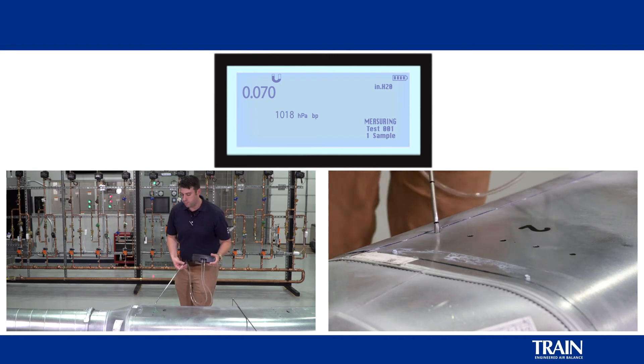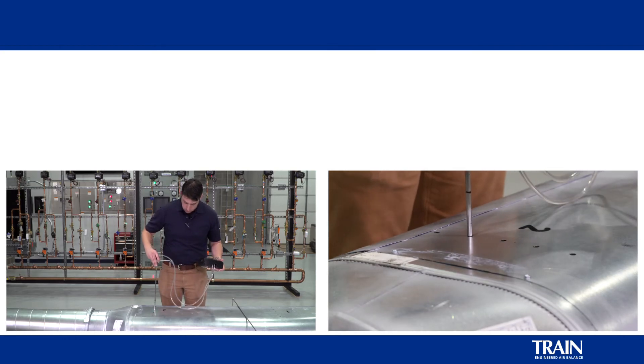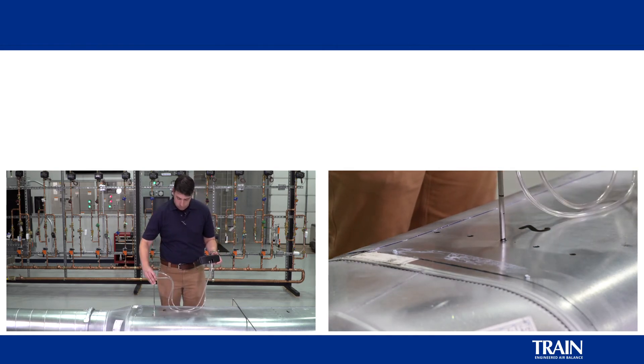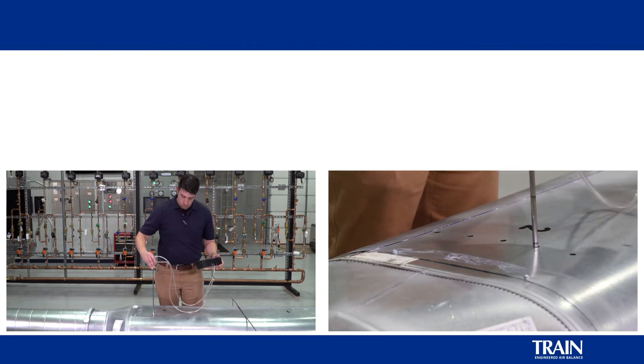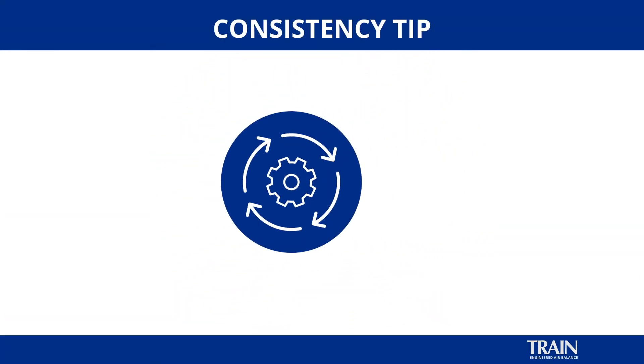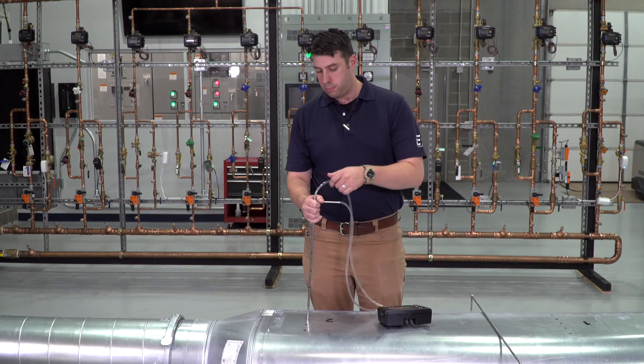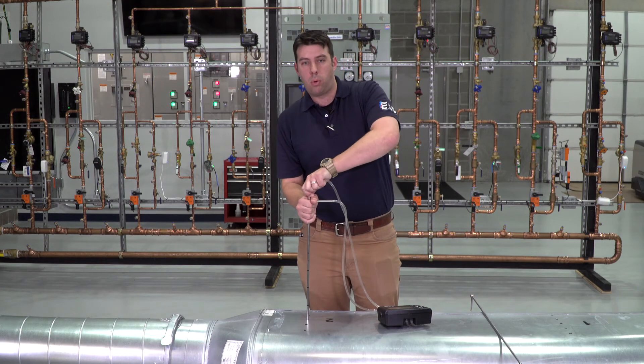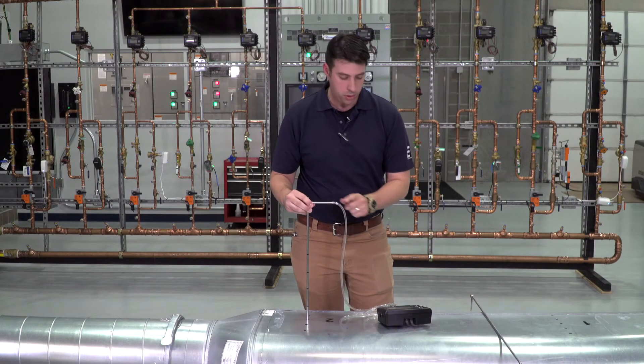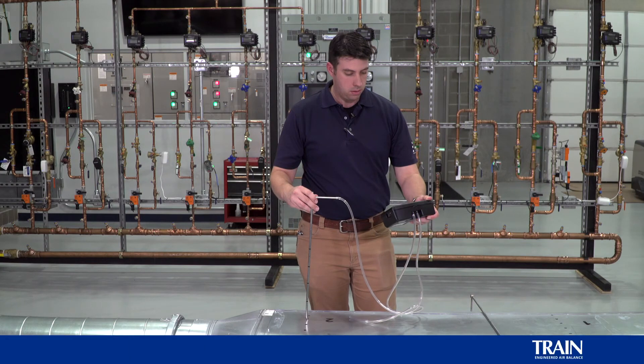For the sake of speed, we're going to go through the next holes a little bit more quickly. We also want to make sure that we perform a static pressure measurement. To do this, we will remove the hose that is connected to the total pressure port of the pitot tube so that the only hose remaining on the pitot tube is on the static pressure port. We will then record this value for the traverse.